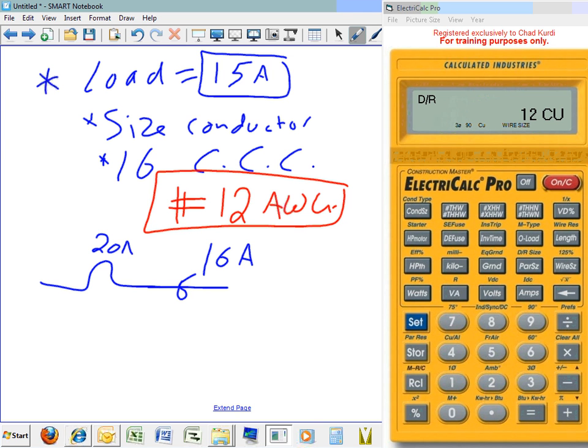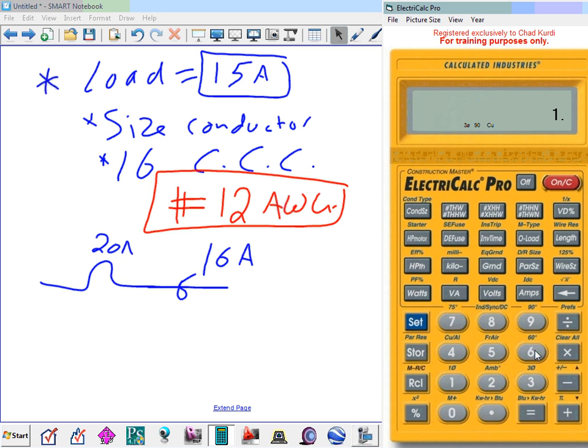Why 16? Because that's the max I can pull as continuous load. 16 amps. Go size this conductor for me, Chad, based on these circumstances. All you have to do, guys, is hit 16 amps, because your calculator is still set up the same way, amps, right? Hit 16 again, and set conductor, and derate. What did you get? Number 10.